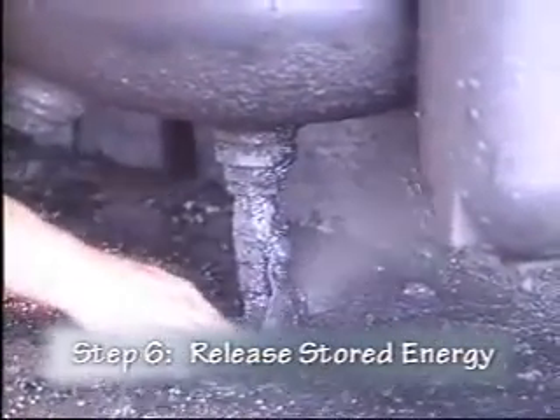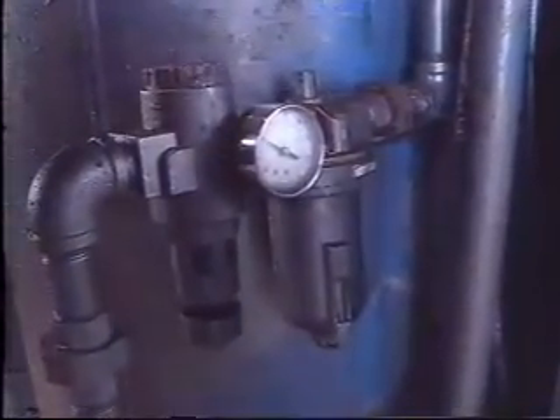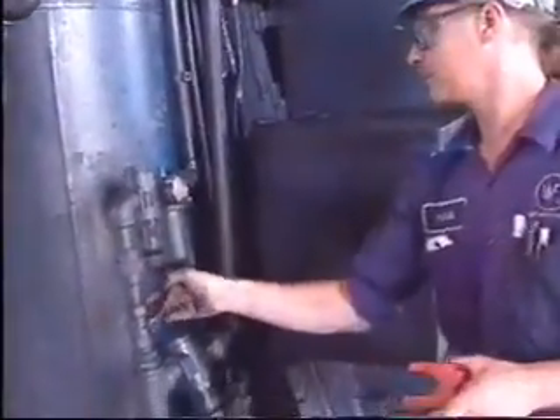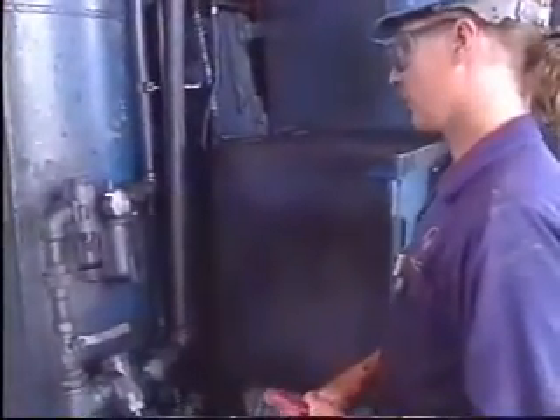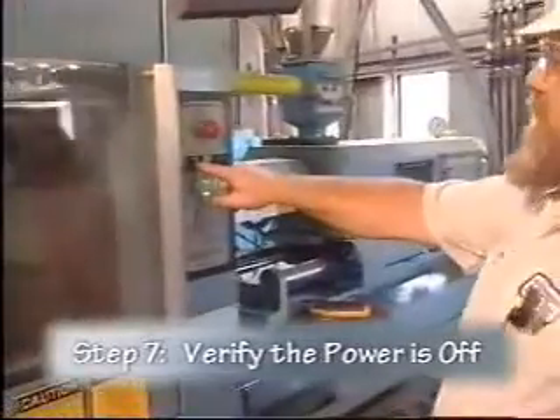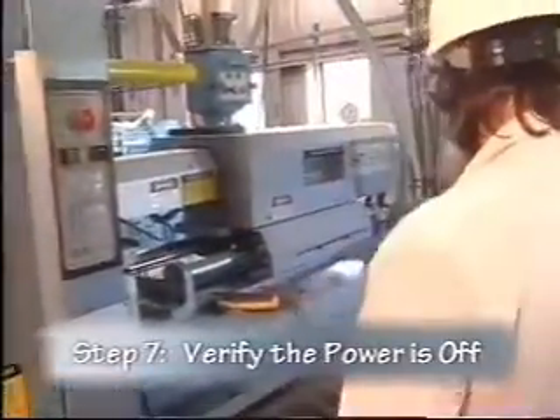Step 6. Release or secure any stored energy. This may involve draining valves, releasing hydraulic pressure, blocking moving parts, or however it's detailed in your company's procedures. Step 7. Try to restart the machine to verify that the power is shut off. Then, return the machine switch to the off position.